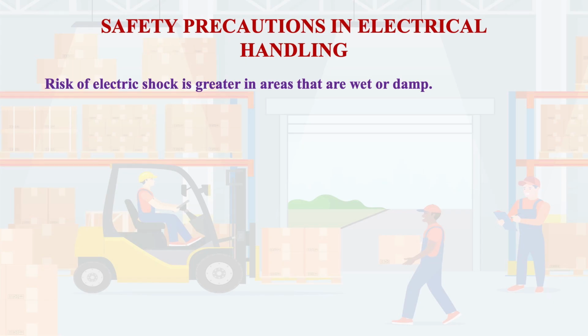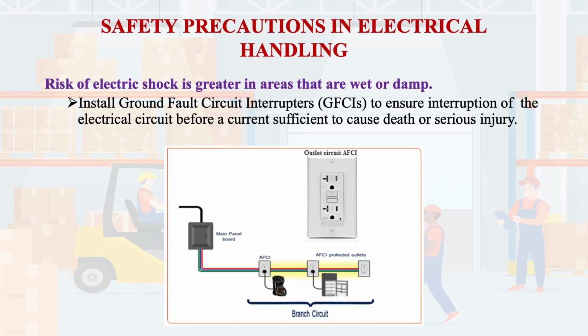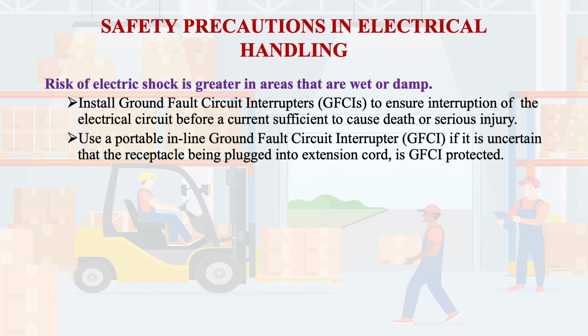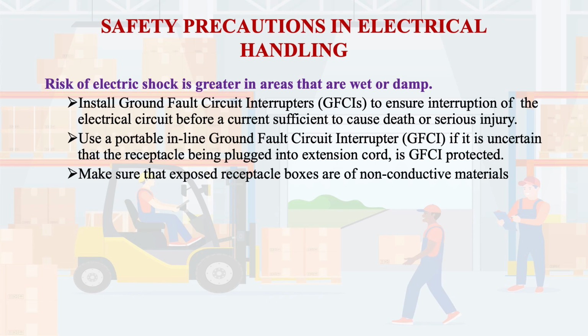The risk of electric shock is greater in areas that are wet or damp. The reason is that water is a good conductor of electricity. Therefore, wet areas will be more prone to electrical shocks. You should take remedial measures, that is, install ground fault circuit interrupters, GFCIs, to interrupt the electrical circuit before a current sufficient to cause death or serious injury flows. Use a portable inline ground fault circuit interrupter, GFCI, if it is uncertain that the receptacle being plugged into by the extension cord is GFCI protected. Make sure that exposed receptacle boxes are of non-conductive materials. This is very important because a conductive metal will naturally result in electric shock.